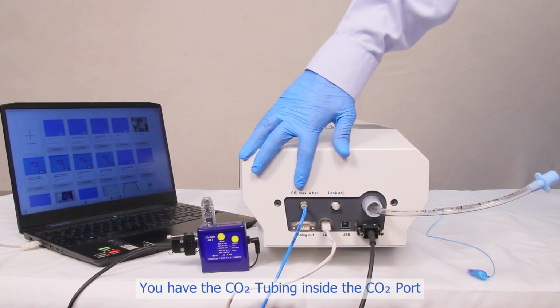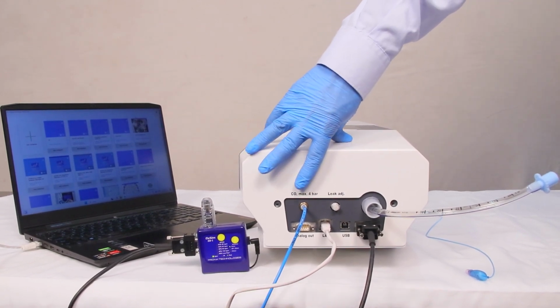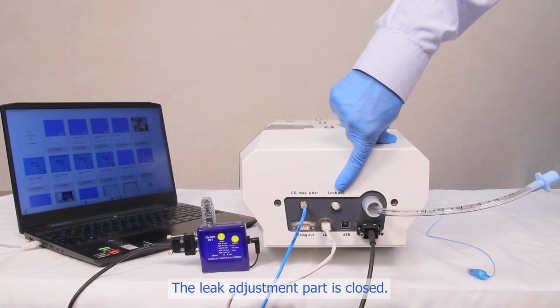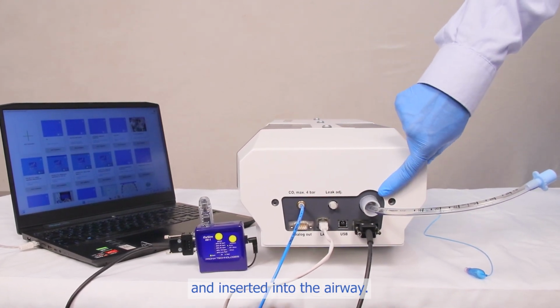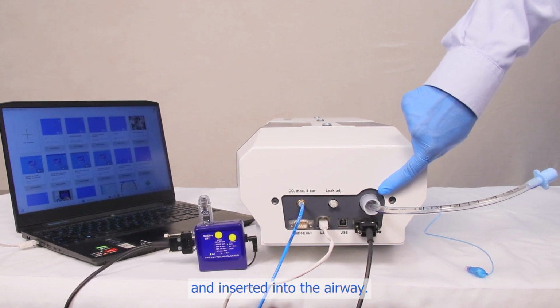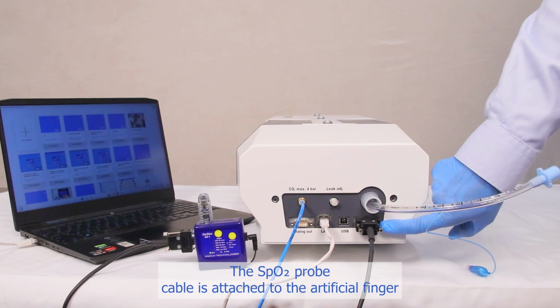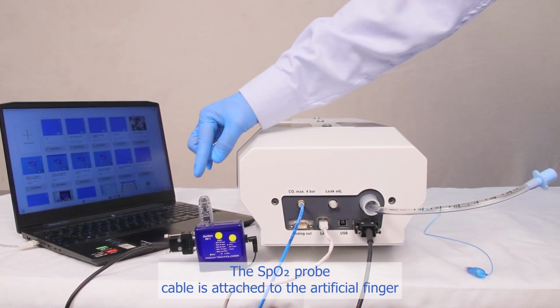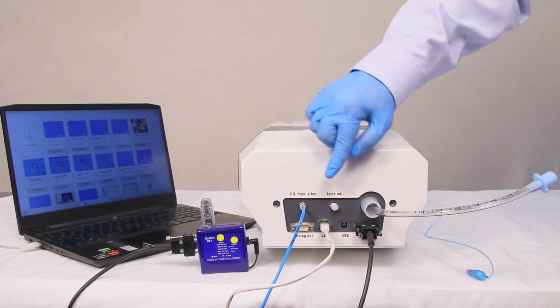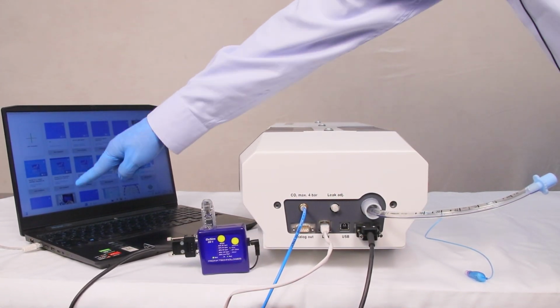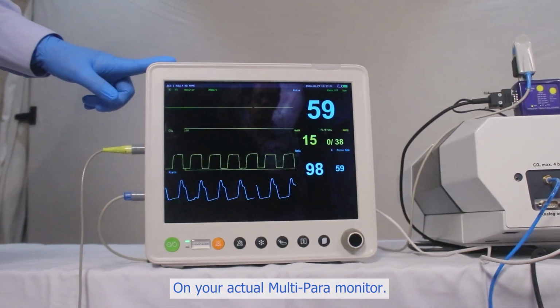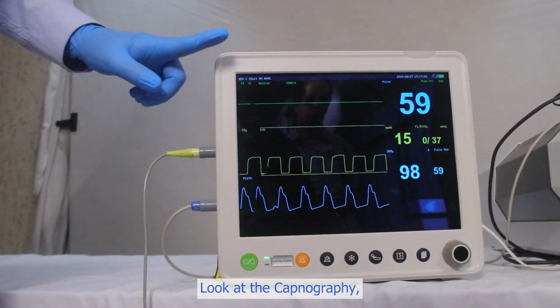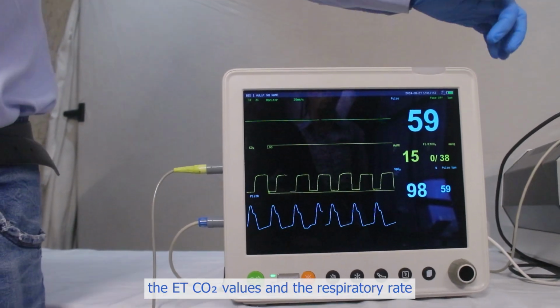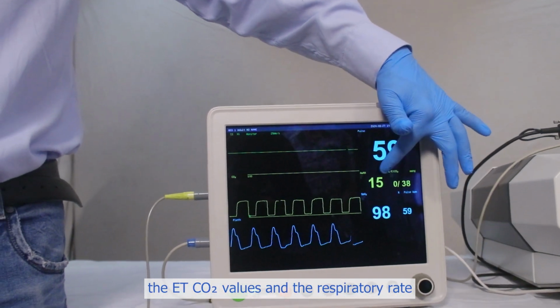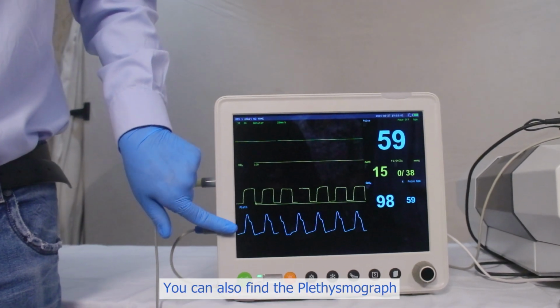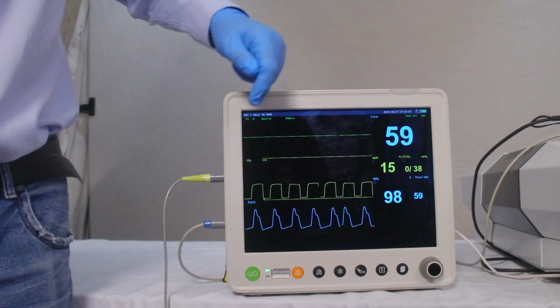You have the CO2 tubing inside the CO2 port. The leak adjustment part is closed. The ET tube is attached and inserted into the airway. The SpO2 probe cable is attached to the artificial finger, and the LAN cable is attached to the laptop. On your actual multi-para monitor, look at the capnography, the EtCO2 values and the respiratory rate. You can also find the plethysmograph and the saturation.